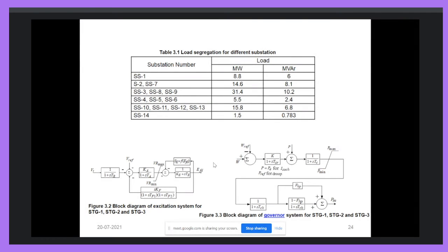So active power balance will be maintained by using the governor. But the governor is not sufficient to maintain the active power balance, because whatever mechanical power we have available, we can generate electrical power according to that. We have limited mechanical power input. Mechanical power input is given with the help of a turbine, which is driven by steam. The governor only changes the speed. The input of steam is changed with the help of this governing system, and it works on the basis of the frequency of the system. So the governor will vary the mechanical input power according to the load demand, but only in a limited range.